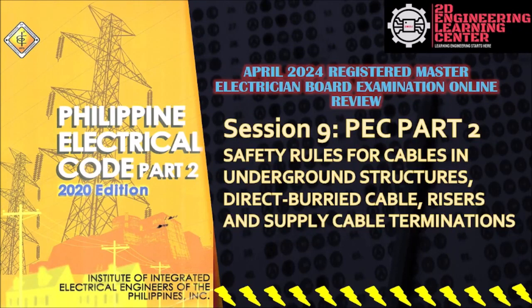Cables, underground structures, direct buried cable, risers, and supply cable termination. So last time, what we discussed was all about the safety rules for underground supply lines and communication lines. For today, we'll go to the underground structures, the underground structures that support our conductors or cables. If the cable is also not put in a conduit, so it's not placed in a conduit, directly buried lang.